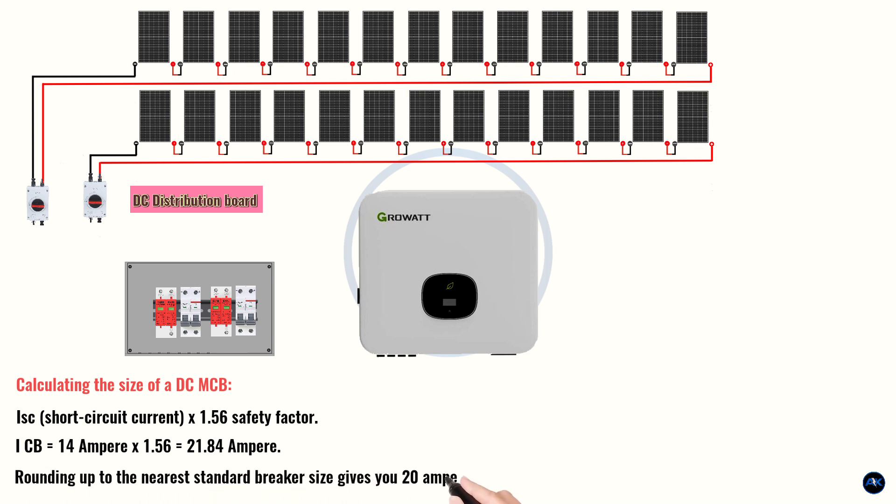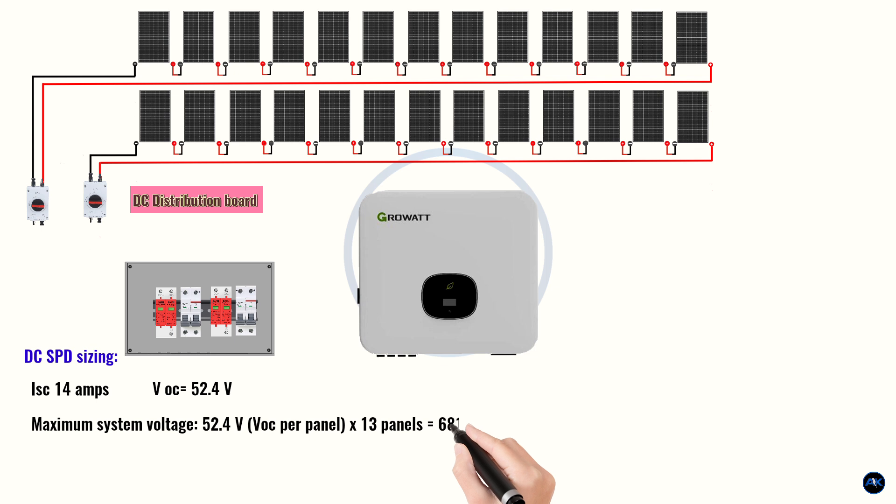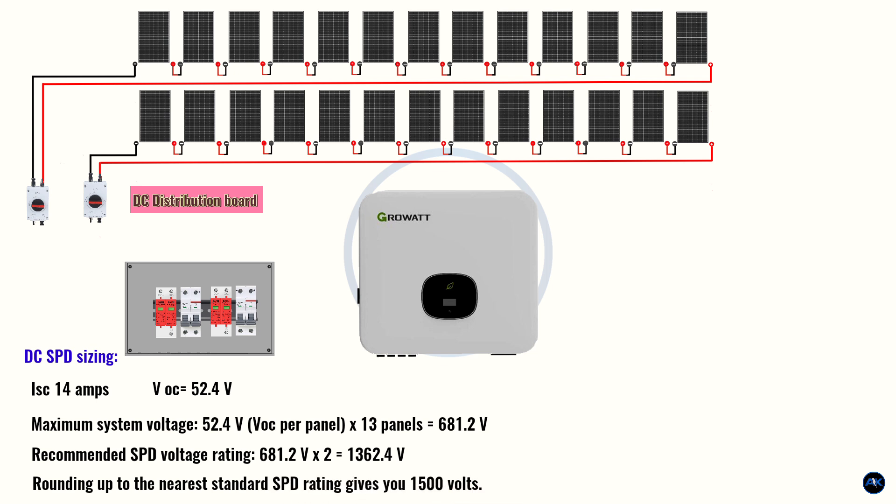DC SPD sizing. For a solar string with 13 solar panels connected in series, each having an ISC of 14 amperes and a VOC of 52.4 volts, the recommended DC SPD size would be 1500 volts. Here's the calculation: maximum system voltage 52.4V VOC per panel X 13 panels equals 681.2 voltage. Recommended SPD voltage rating: 681.2V X 2 equals 1362.4 voltage. Rounding up to the nearest standard SPD rating gives you 1500 volts. Additional factors to consider: number of strings. If you have multiple strings, each string should have its own SPD.